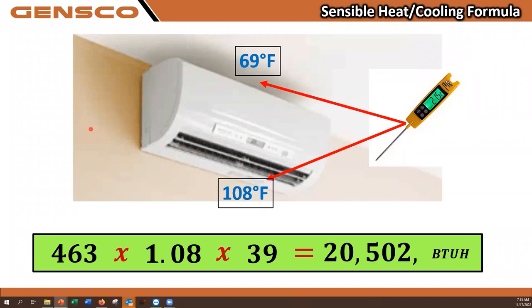Now, if someone was complaining they have insufficient heat, this obviously dispels any thoughts that it's a unit problem. It could be the house is too large for the unit. Don't want to say the unit's too small, but that could be a possibility. Or in the case of an actual job site visit I made, where these numbers came from, this was a house that had a lot of high back furniture about 12 feet in front of this unit, which prevented the heat from going any further in the house and produced their complaints. The unit didn't have a problem heating. It had a problem heating where they wanted it to go. So that in a nutshell is a sensible heating, or this could have been a cooling sensible calculation.